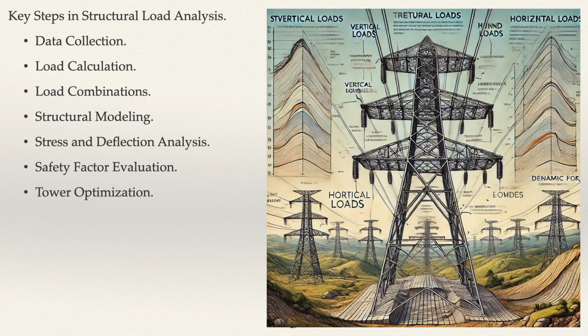Key steps in structural load analysis. 1. Data collection. A. Environmental data: wind speed, ice thickness, seismic zone information, and temperature variations. B. Conductor data: size, tension, and sag characteristics of conductors and shielding wires. C. Tower data: dimensions, materials, and tower type, e.g. suspension, angle, tension.